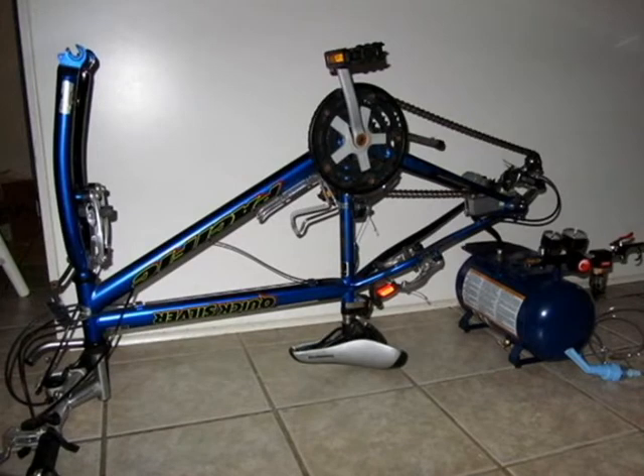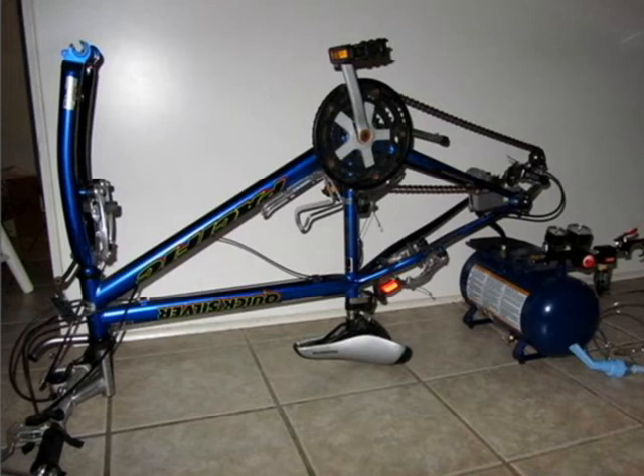What we've done is currently all the nebulizers on the market, or most of them, use electricity or battery to power a motor. And the motor turns a reciprocating air compressor that compresses the air to the nebulizer tubing. And so we took out the motor and we replaced it with a set of gears and a human that would run those gears. For our project, we used a bicycle. As you can see, we've turned the bicycle upside down, and the reciprocating air compressor is right here, connected to the bicycle.